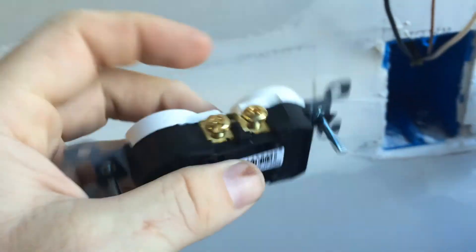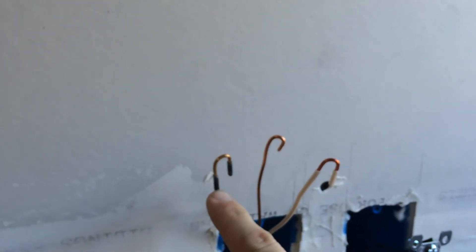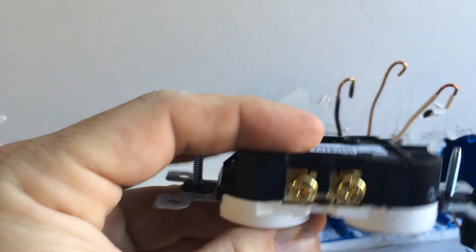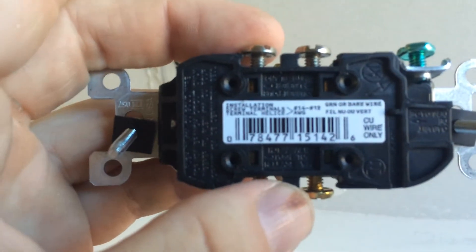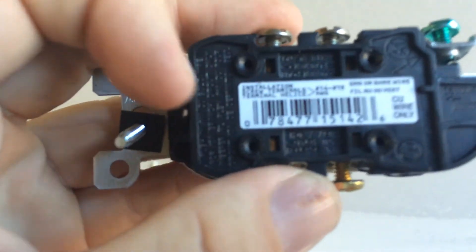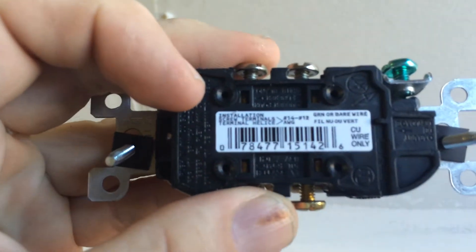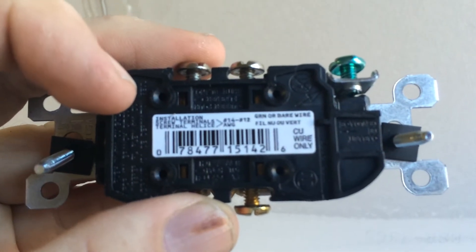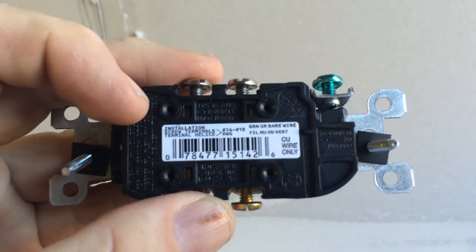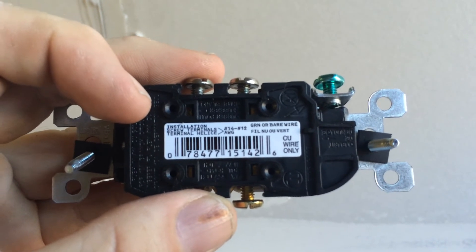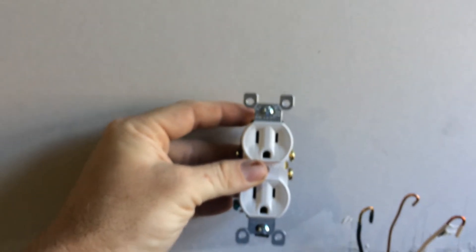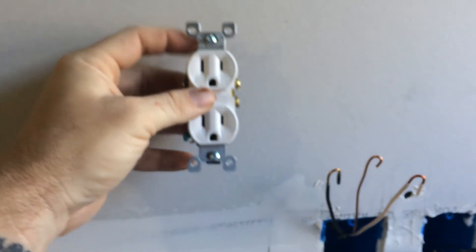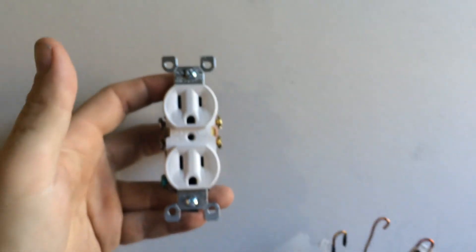What I do is I normally strip a little bit off, and then I take another little chunk and move it to the very end of both your hot and your neutral. I bend it and I actually attach it to the screws instead of using the holes back there for backstabbing your receptacle. Like I said, I don't recommend doing it. As an electrician, you can do it if you want and I'll come back and fix your stuff someday. It's not a big deal, I get paid pretty good money to do it.